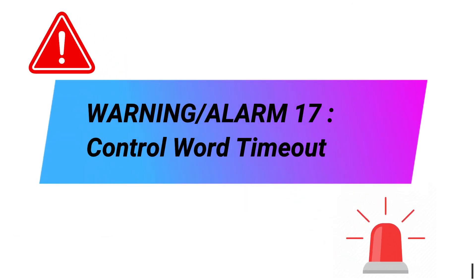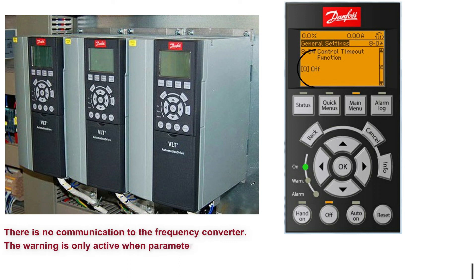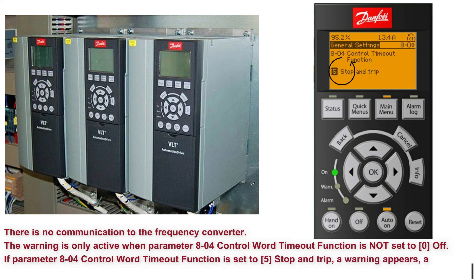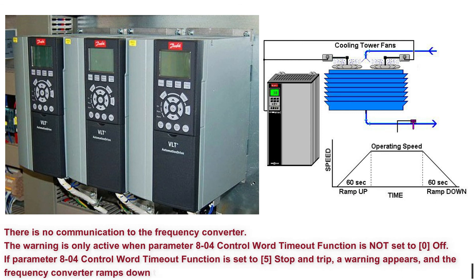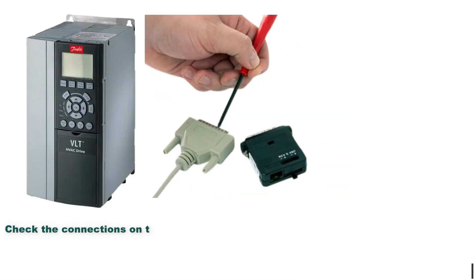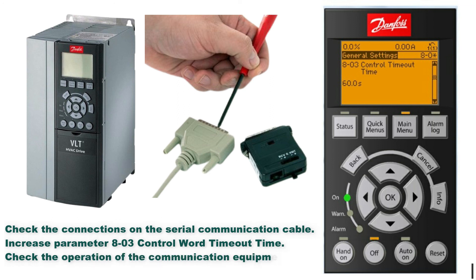Warning. Alarm 17: Control word timeout. There is no communication to the frequency converter. The warning is only active when parameter 8-04 control word timeout function is not set to 0 (Off). If parameter 8-04 control word timeout function is set to 5 (stop and trip), a warning appears and the frequency converter ramps down to a stop and shows an alarm. Troubleshooting methods: Check the connections on the serial communication cable. Increase parameter 803 control word timeout time. Check the operation of the communication equipment. Verify that proper EMC installation was performed.